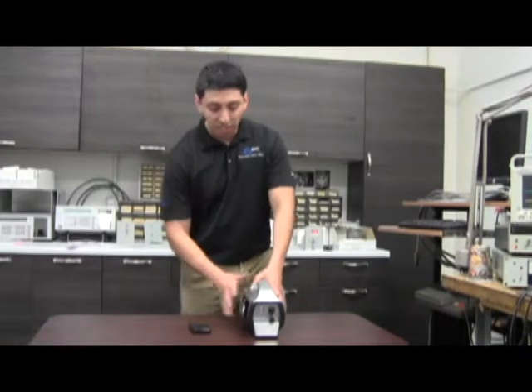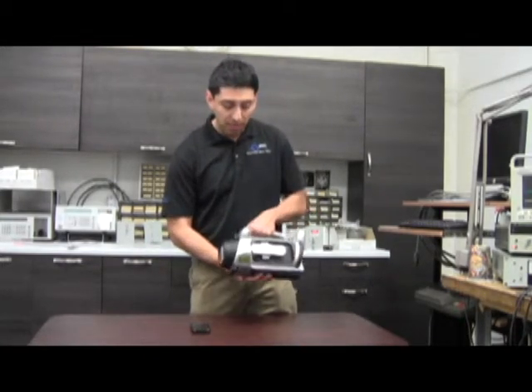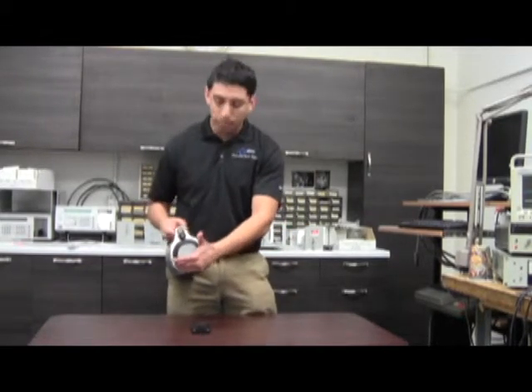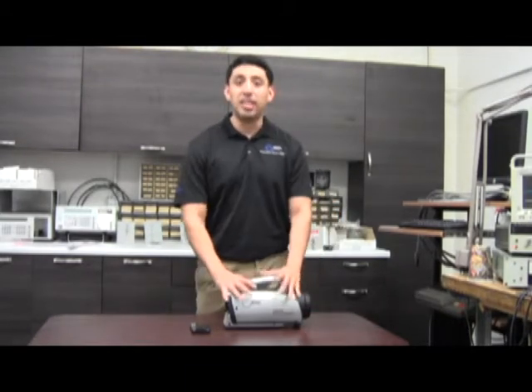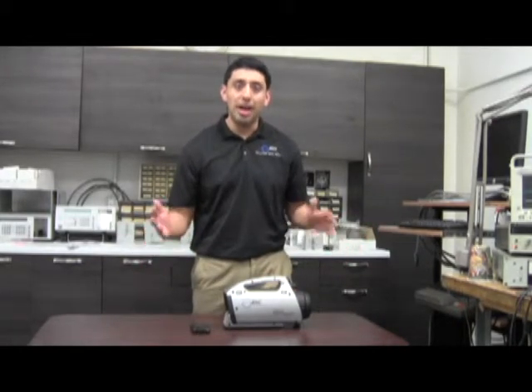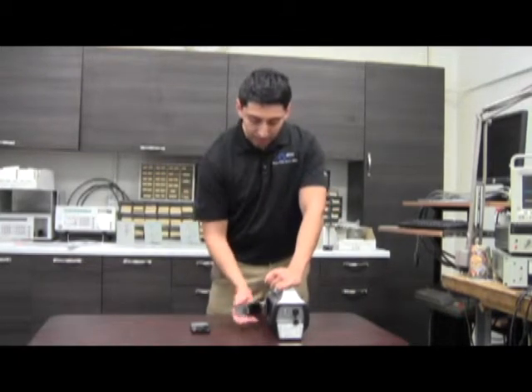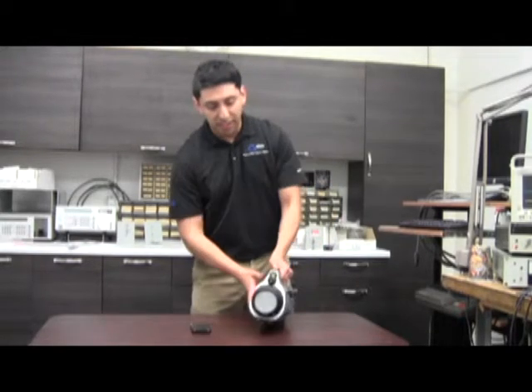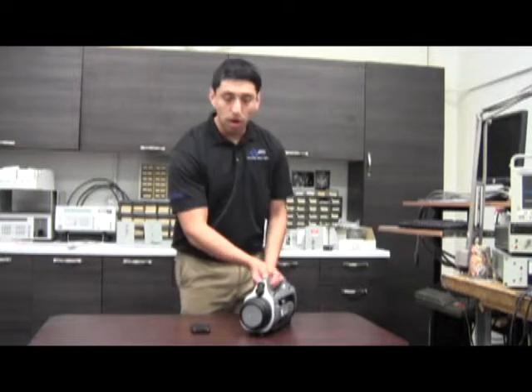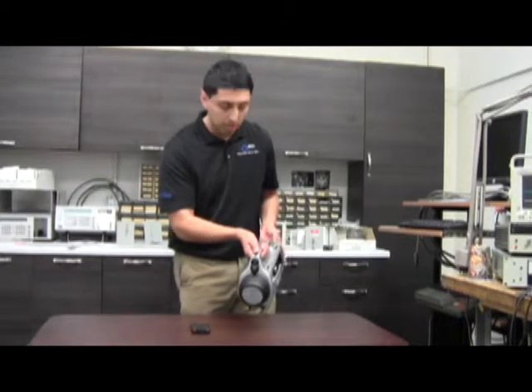Right here you have your detector and your PDA — that's pretty much all you'll need to get started. We've definitely improved our SAM 945 from our older 940: very rugged, hard casing, and we no longer have that external detector. The unit comes standard with a 3x3 sodium iodide, but we also offer lanthanum bromide and cerium bromide. All units include a GM detector for high dose rate. Another feature we've added is the laser, which gives you a good indication of how far you are from a source, and a flashlight for dark or poorly lit environments.